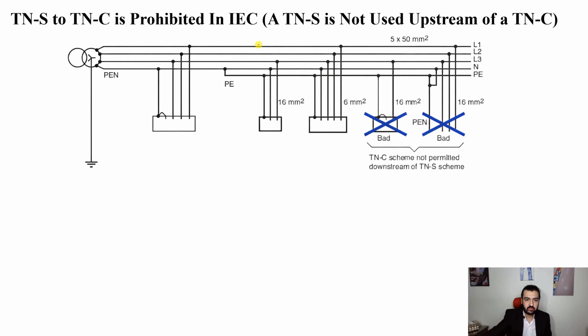Okay, let's look at this system. So we have PEN, TN-C converted into 5 wires, which is TN-S. Great. Now as we go, you can see at this particular point we converted into TN-C. How do I know? You can see protective earth, you can see neutral, protective earth. They are combined into 1 wire going to the load, PEN. So we had TN-S, then TN-C. Now, is this allowable? No.